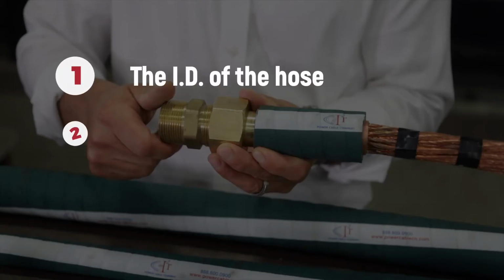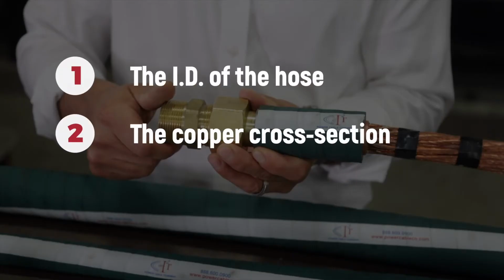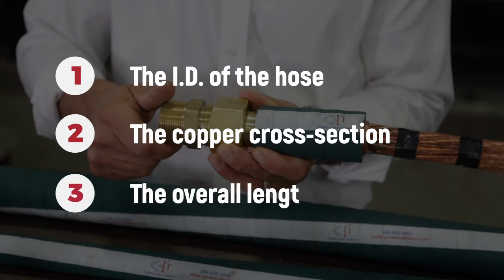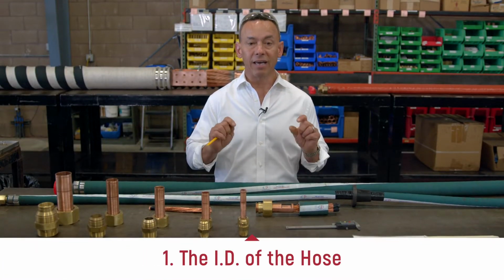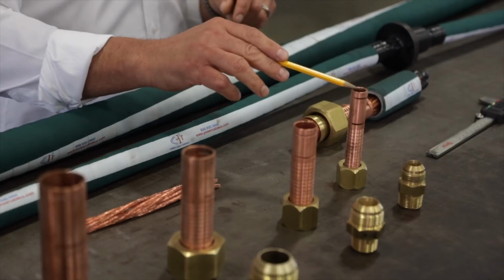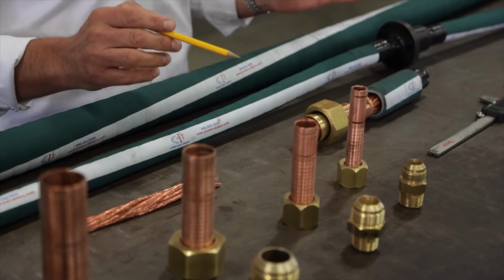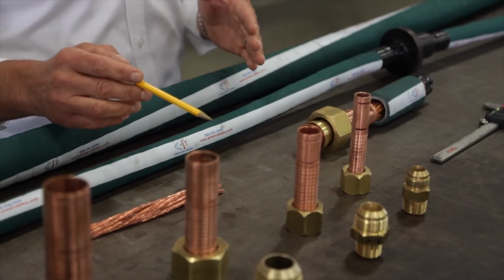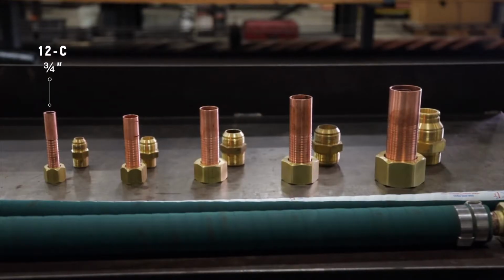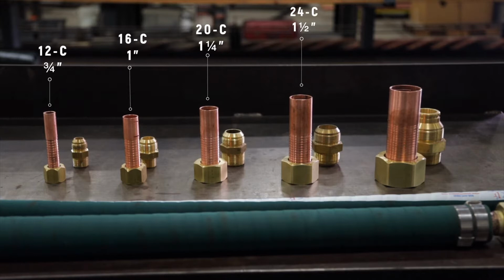One is the ID of the hose, two is the copper cross section, and three is the overall length of the cable. The ID of the hose is largely determined by a C increment. A 12C is a 3/4 inch ID hose, and a 16C is a 1 inch ID hose, and it moves in 4C increments. So I go 12, 16, 20 is an inch and a quarter, 24C is inch and a half, and a 32C like this would be a 2-inch ID hose.